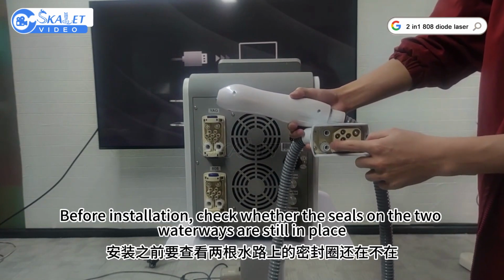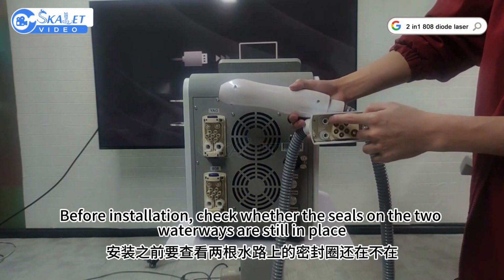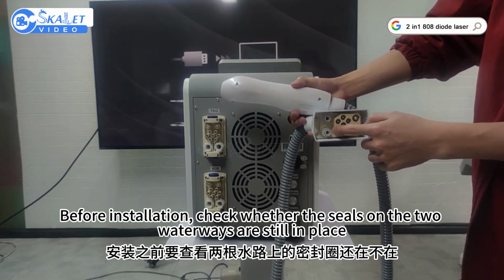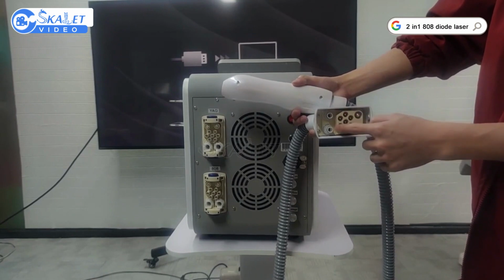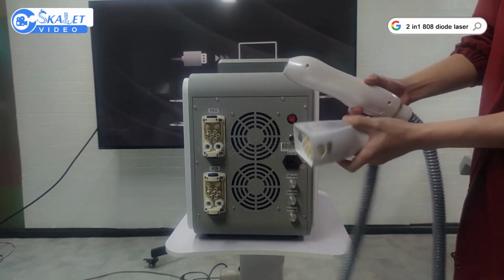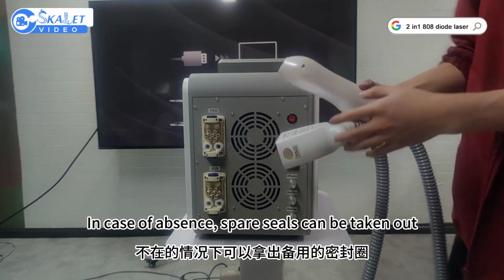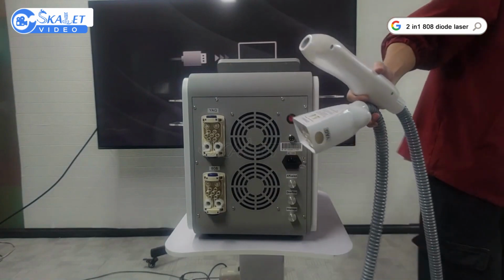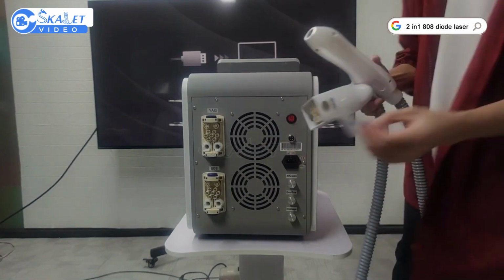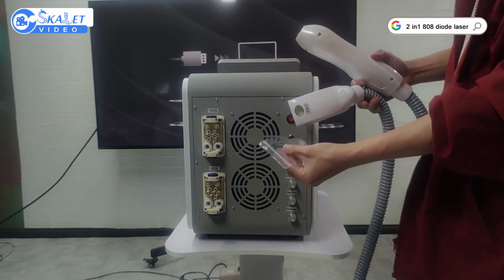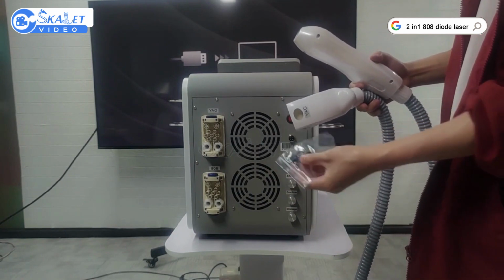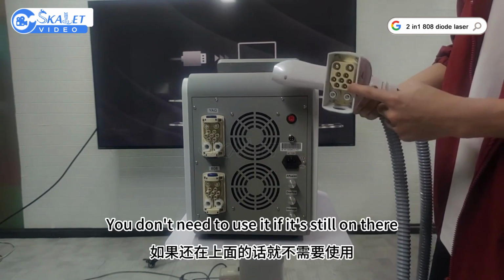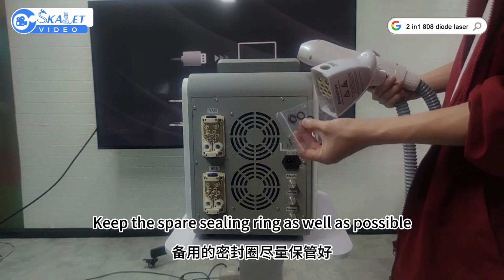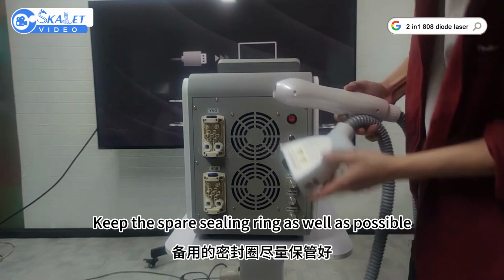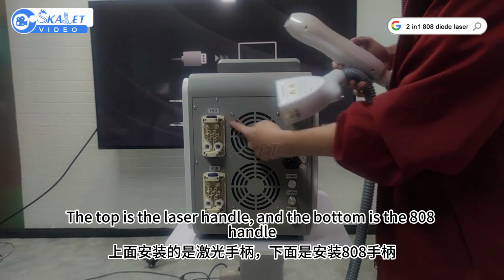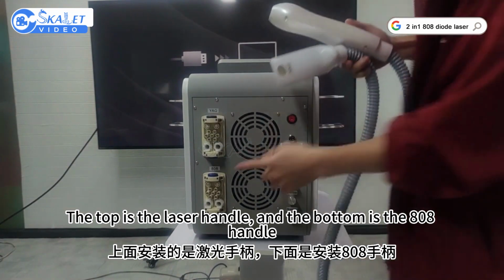Before installation, check whether the seals on the 2 waterways are still in place. In case of absence, spare seals can be taken out. You don't need to use it if it's still on there. Keep the spare sealing ring as well as possible. The top is the laser handle, and the bottom is the 808 handle.